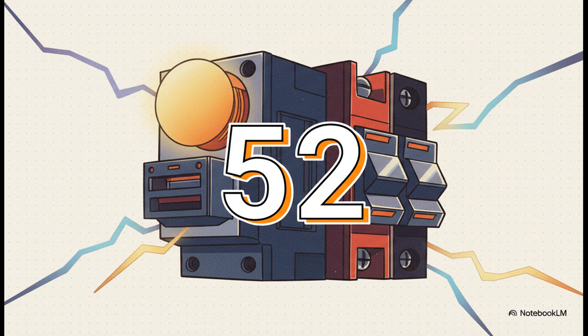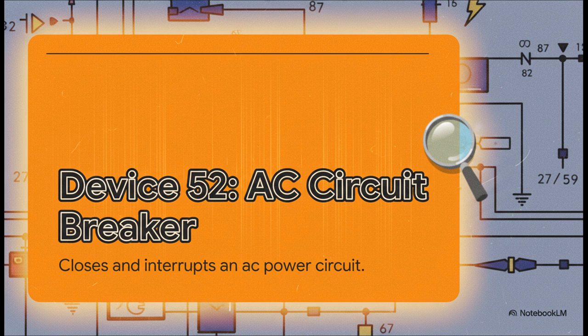So if the 50 and 51 relays are the detectives that spot the problem and sound the alarm, who's the one that actually kicks down the door? Well, that would be device 52. Device 52 is the AC circuit breaker. This is the muscle of the whole operation.